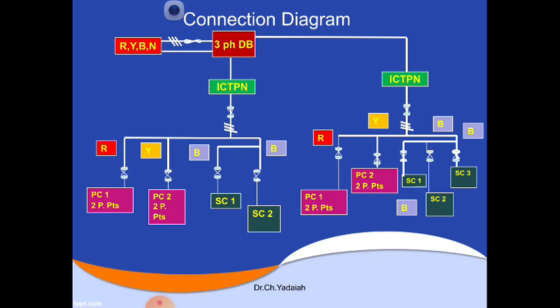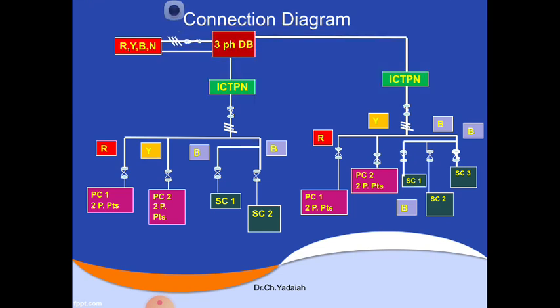Now similarly, going to the first floor. In the first floor also, to control this, we are using another controlling device, the iron clad triple pole with a neutral link, provided just like protective equipment. From these three phases R, Y and B, here also the R phase is connected to the power circuit and the Y phase is also connected to the power circuits, and the B phase is connected to only the lighting load. That means the first floor and second floor both have only lighting loads on B, whereas R phase and Y phase are connected to the power loads, which draw power as per their capacity.